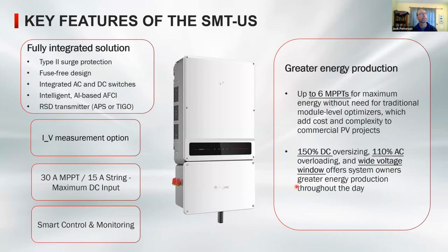The features of this: it's a 480 volt inverter, and it's good for delta or Y secondary winding configurations. So that means basically it can take it with or without a neutral. There are some additional perks. It has surge protection on the AC and DC side. It has AC and DC switches. It also has a very intelligent AFCI, considered intelligent because it's AI based. It keeps learning, so it's a very sophisticated AFCI.